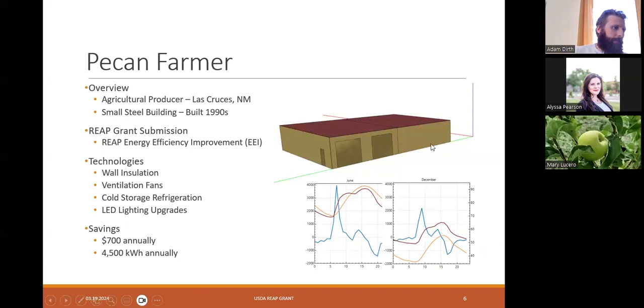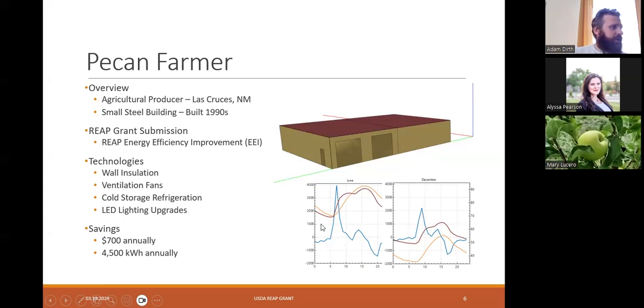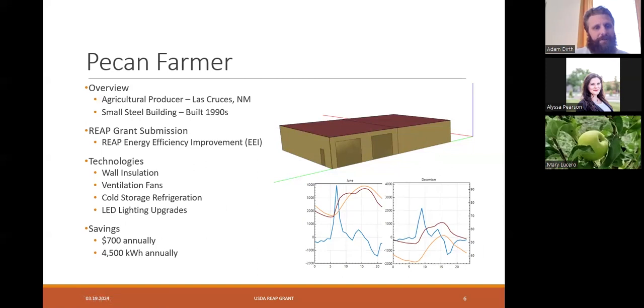We created a building energy model for their facility that showed how different energy technologies save energy and improve occupant comfort. The data shows that with wall insulation and ventilation fans, the temperature in the building becomes more manageable — peaking out at 90 degrees down to closer to 70–75 degrees. They applied for the REAP energy efficiency improvement grant (EEI), and the technologies included wall insulation, ventilation fans, cold storage refrigeration, and LED lighting upgrades. You can see the financial and energy savings at the bottom.